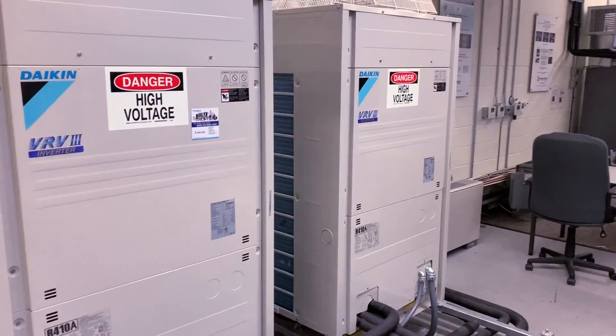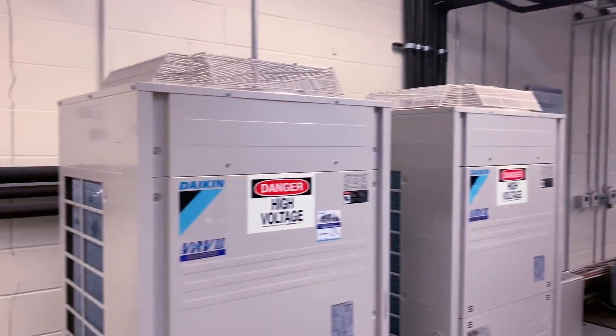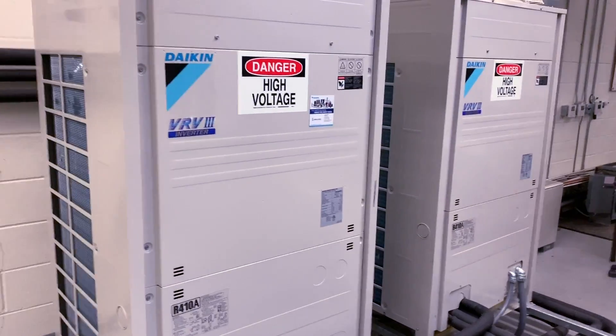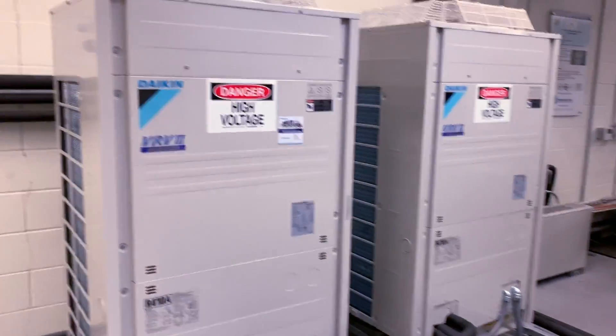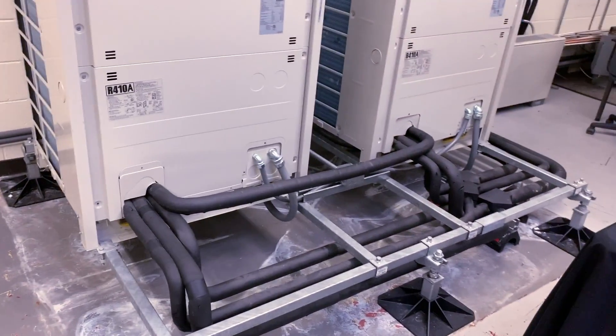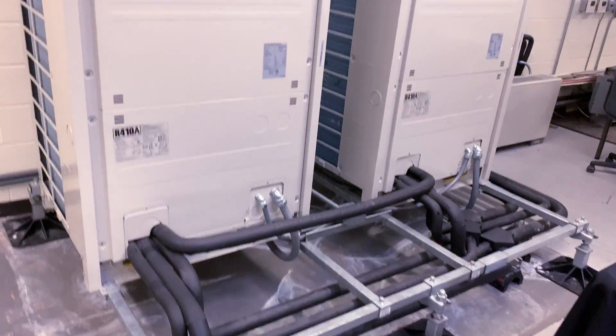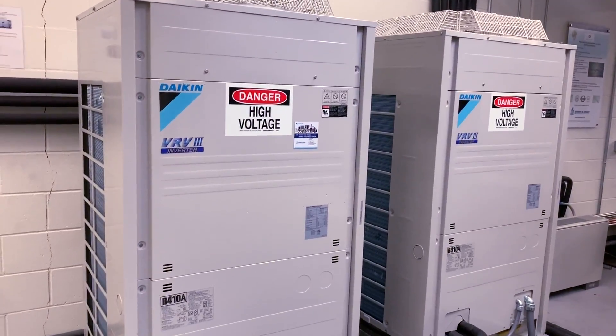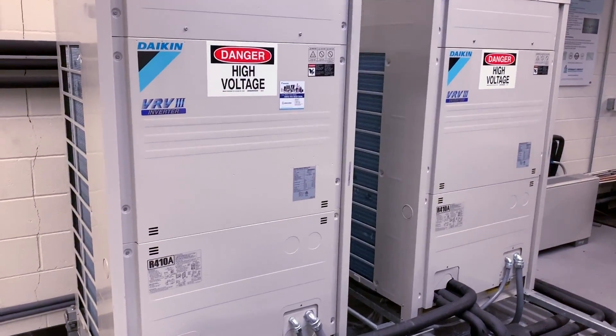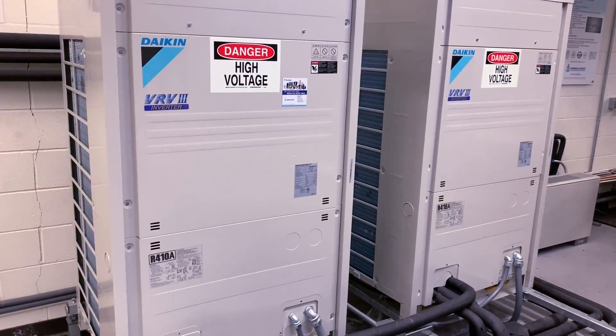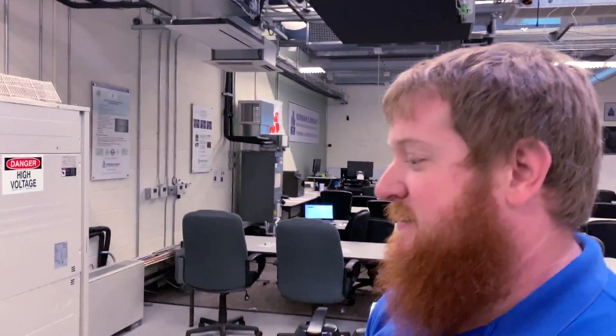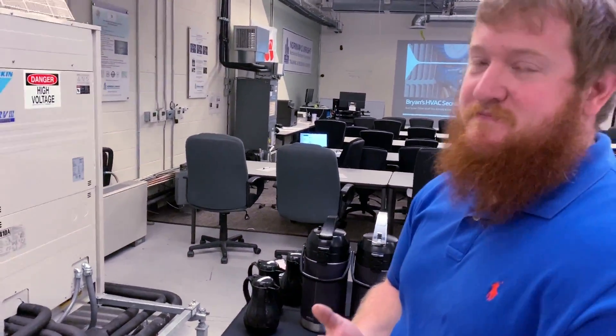You touched on it already, read the book. The biggest thing we can tell people is if the piping network on the outside follows the rules that Daikin sets forth, which are pretty simple, there's really nothing to worry about. Proper airflow coming out of the condenser, keeping the coil clean, that's the big service things. You just got to keep the coils clean. In four and a half years of doing this, I've obviously seen my fair share of compressor changeouts, but major failures I've not really seen many.